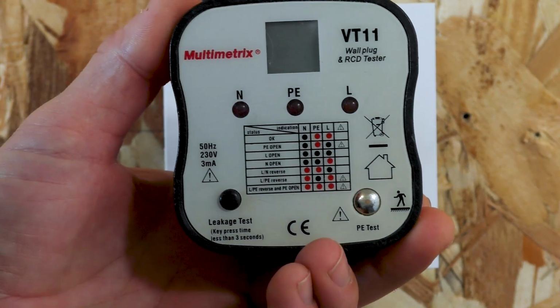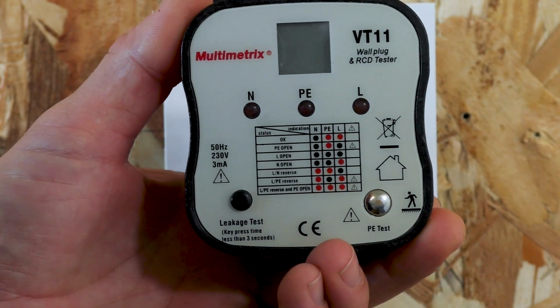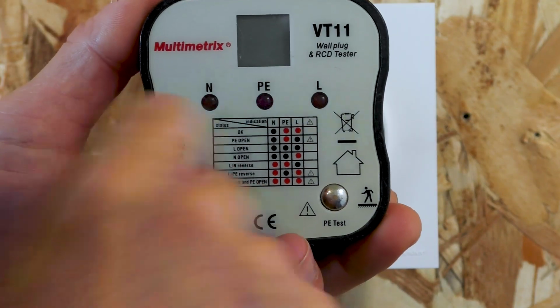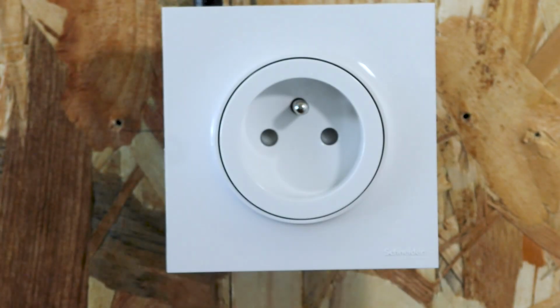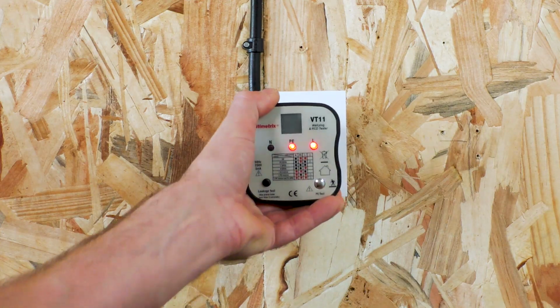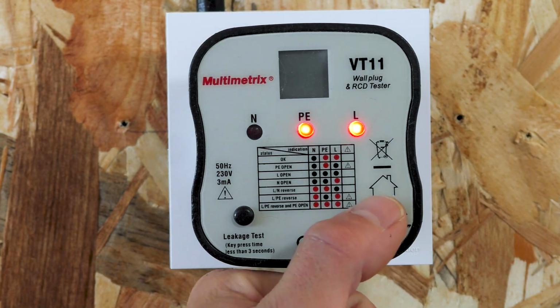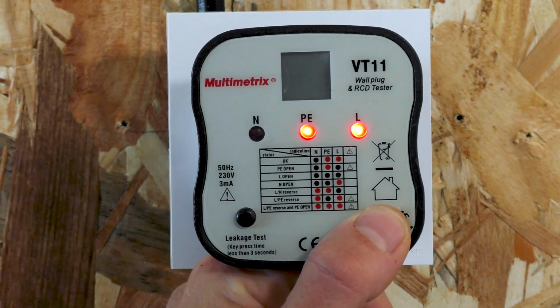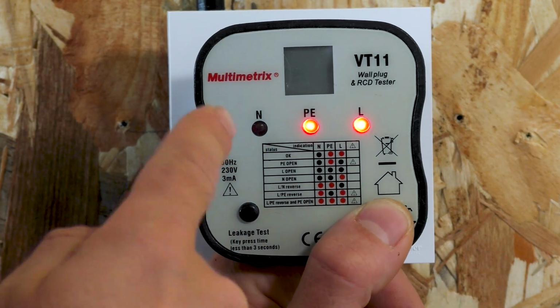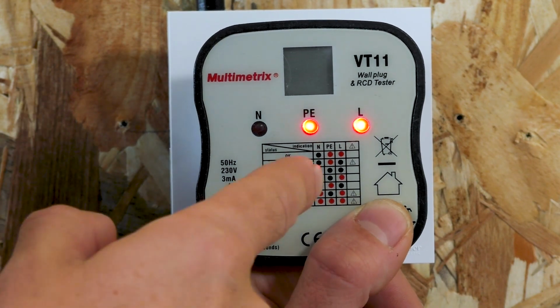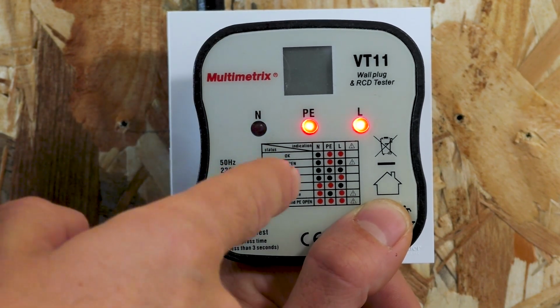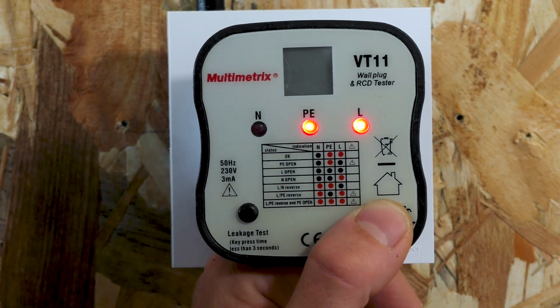If you don't have ground at all, only the middle lamp will light up. If your live and neutral are reversed, the two left lamps will glow up, and so on. If you touch this little metal plate here, and if you see a danger sign on the screen, that means that something is wrong with your grounding. More specifically, a live wire is touching the ground somewhere, and you need to check your installation.